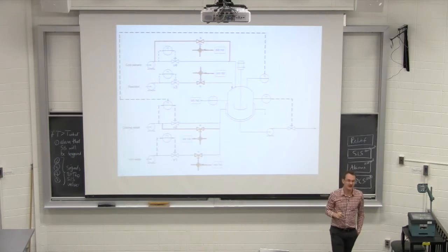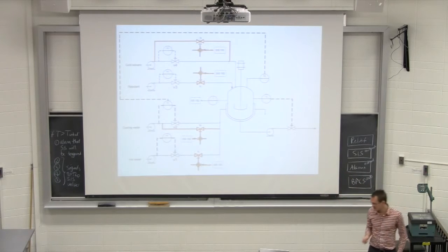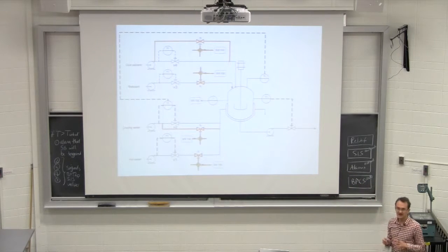They tested it even to that pressure, and they were guaranteeing that the vessel, as long as it's used in the way that it should be used, will not rupture at that pressure. So you can operate the vessel safely at that pressure. You shouldn't normally be operating at the maximum, but it will withstand. And beyond that, you need to provide some form of relief.